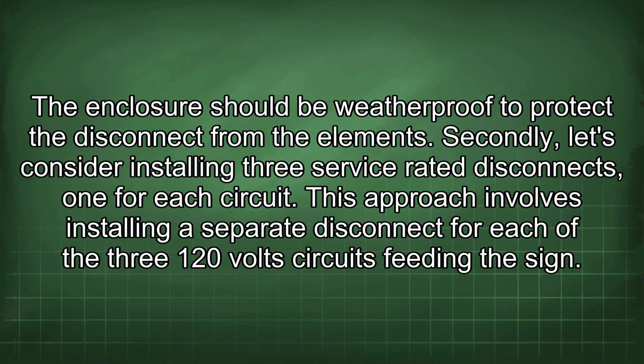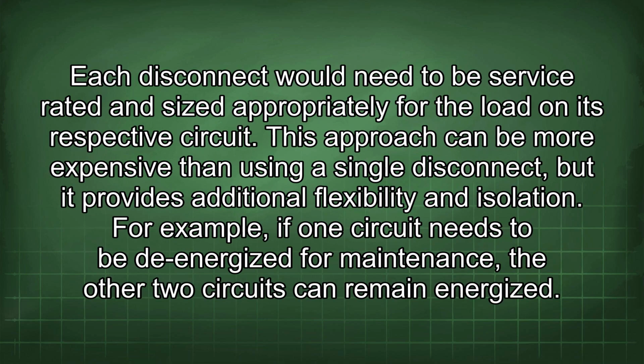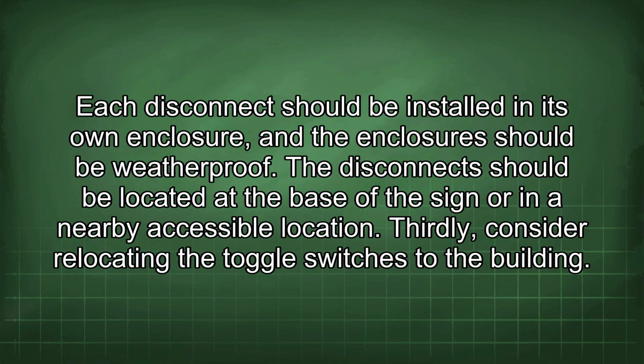Secondly, let's consider installing 3 service-rated disconnects, one for each circuit. This approach involves installing a separate disconnect for each of the 3 120-volt circuits feeding the sign. Each disconnect would need to be service-rated and sized appropriately for the load on its respective circuit. This approach can be more expensive than using a single disconnect, but it provides additional flexibility and isolation. For example, if one circuit needs to be de-energized for maintenance, the other 2 circuits can remain energized. Each disconnect should be installed in its own enclosure, and the enclosures should be weatherproof. The disconnect should be located at the base of the sign or in a nearby accessible location.